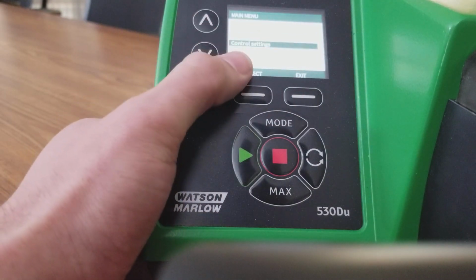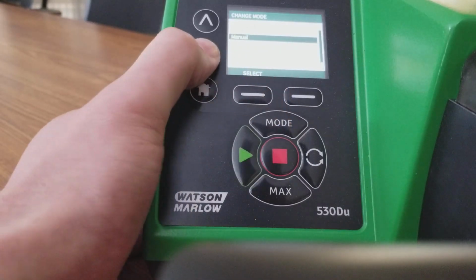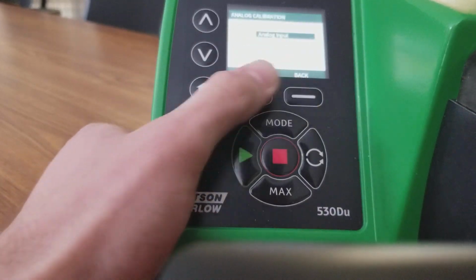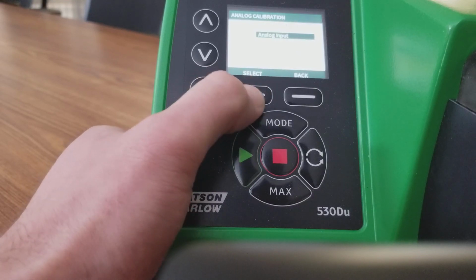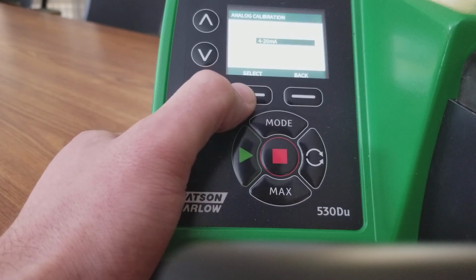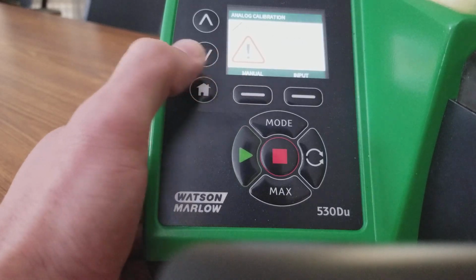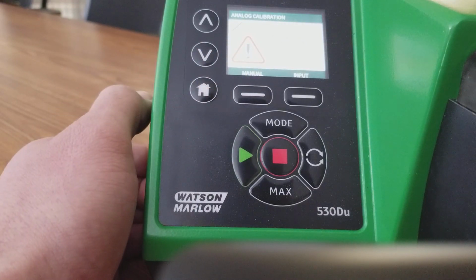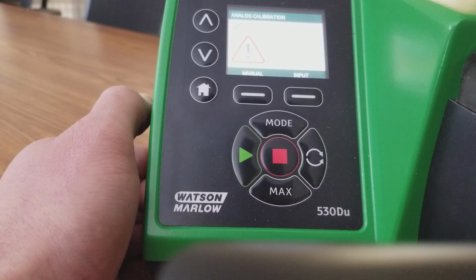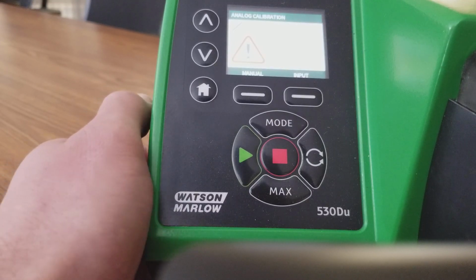After those are set up, we're going to go into our mode menu and go to analog and calibrate it. We want the analog input and we will be dealing with 4 to 20 milliamps, so select that. What you're seeing right now is the manual or input. Manual is, as it seems, I can manually select what my milliamp values will be. Input is the more appropriate way to do it, where they would be sending you a signal from SCADA.